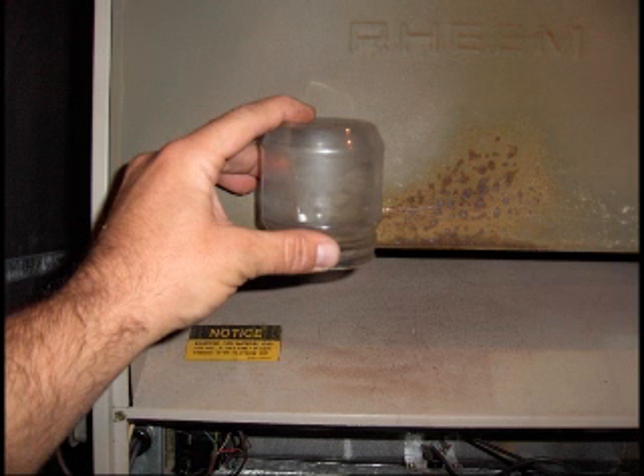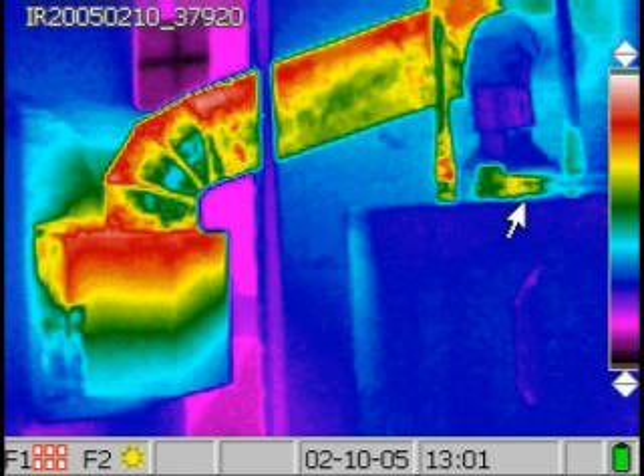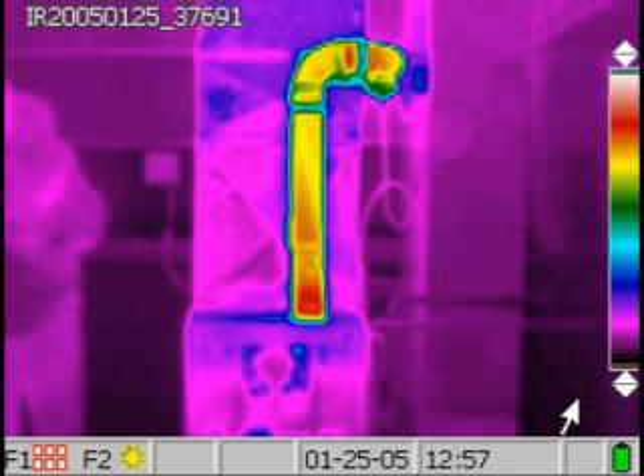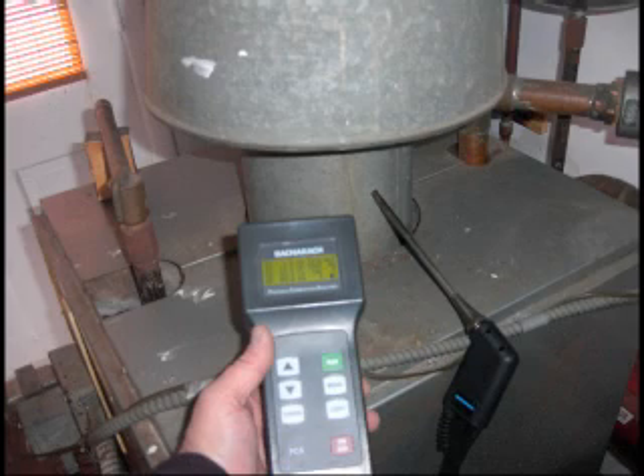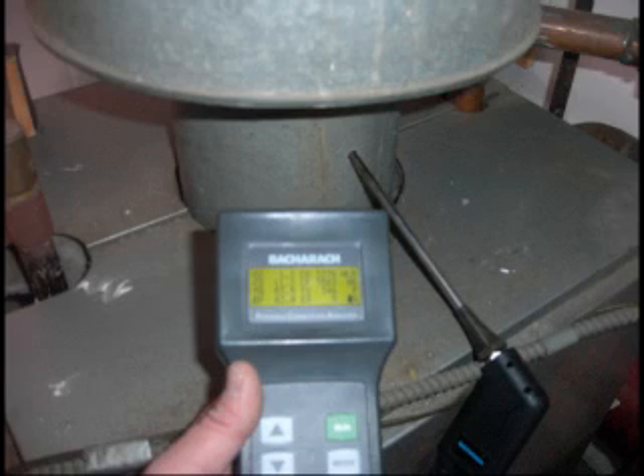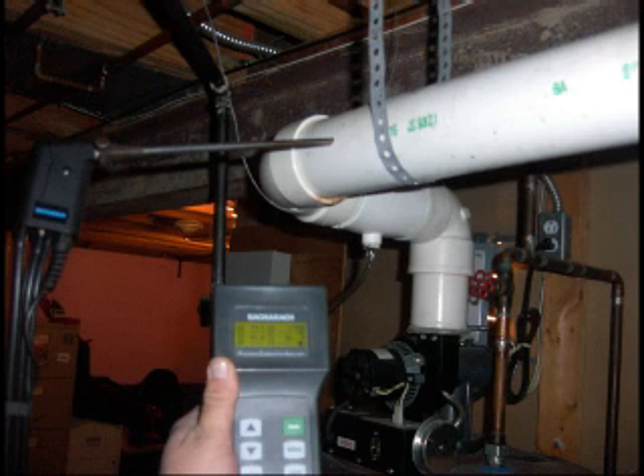Okay, let's get back to the furnace guy, the HVAC contractor. If they don't do a combustion test, then they can't really adjust your furnace, and you could have a lot of problems. Number one, you could be overfired. This means that the gas regulator isn't properly adjusted, and you have a very high stack temperature. You could be underfired. Again, the gas regulator isn't properly adjusted, and you have a low stack temperature. You might have a high oxygen level, and you may even have high carbon monoxide.